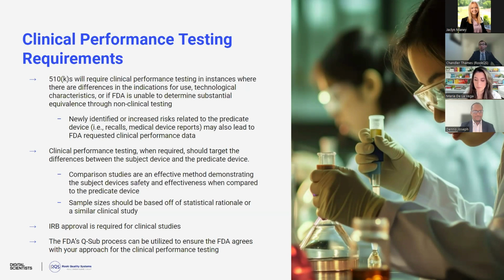So the US government does have a database of all the clinical studies that are performed in the US. You can use keywords or look for competitor devices to find the clinical studies that they've been involved in and use those to pull a sample size. If one's not available, then you would want to lean on that statistical rationale. Another thing to think about is IRB approval is required for clinical studies to make sure that the study itself, being a non-legally marketed medical device and for research use at that stage, is appropriate and safe for the purpose of the clinical study. So if you're planning any clinical studies, definitely need to speak with the IRB, submit a protocol for review and approval, and that will really be the clinical study plan that identifies your protocol, your locations, your sample sizes, as well as your acceptance criteria and the goals of the study.